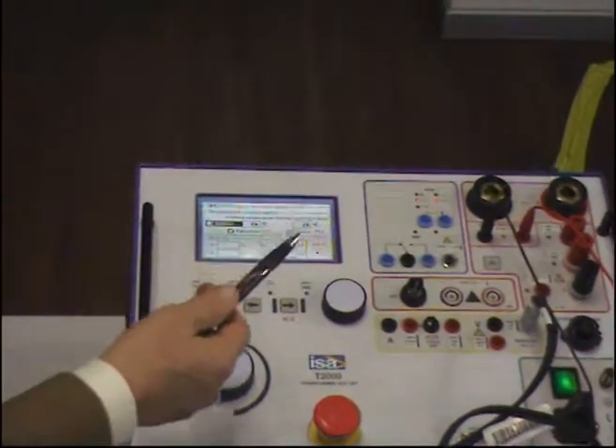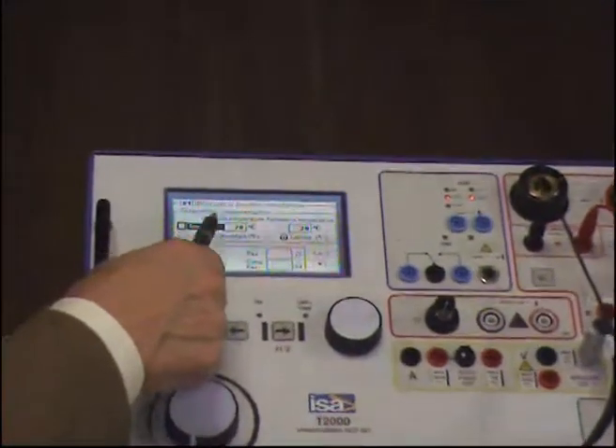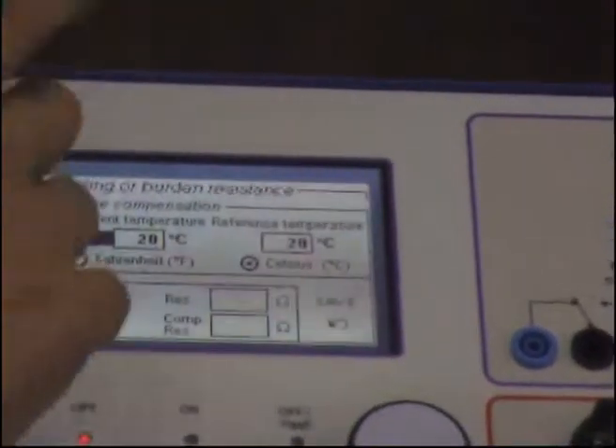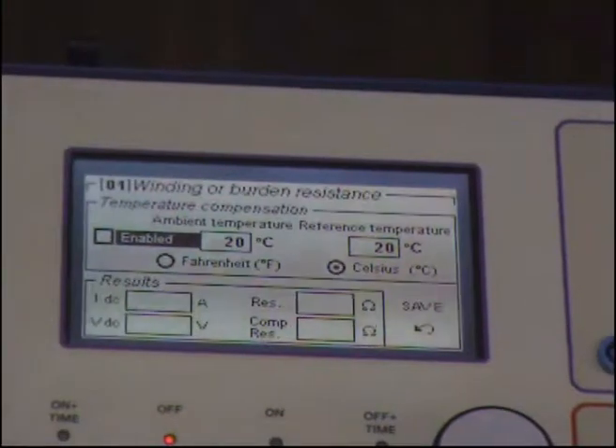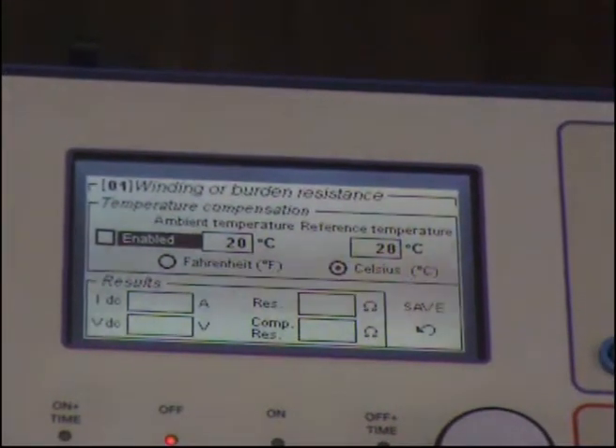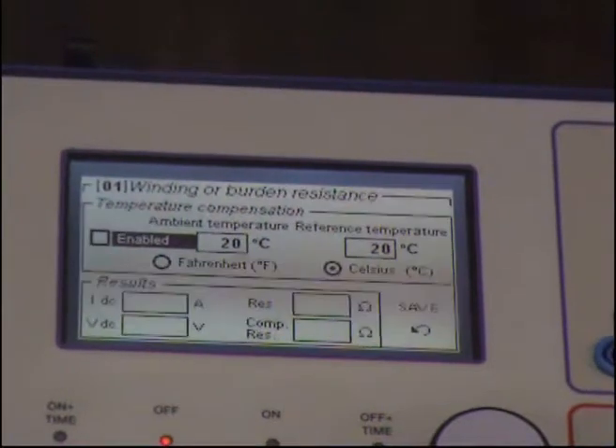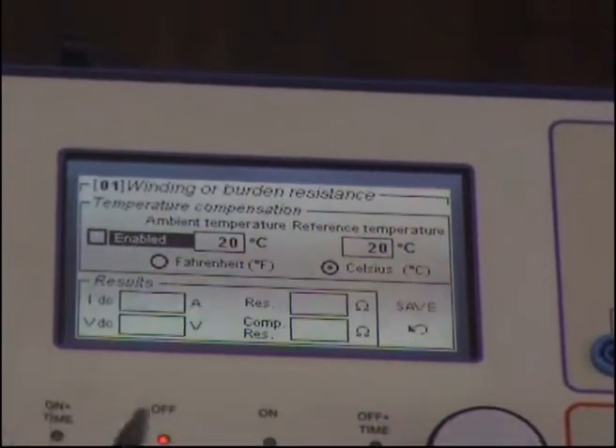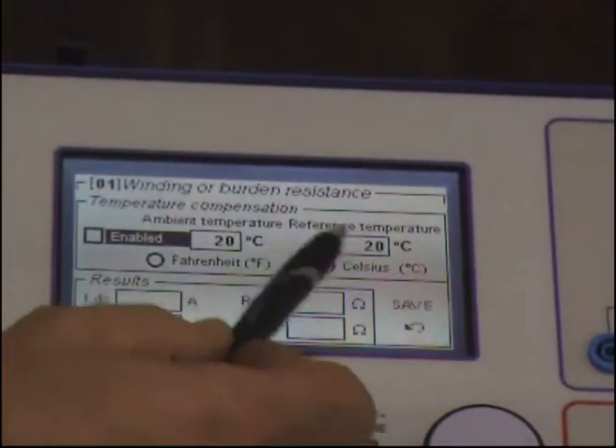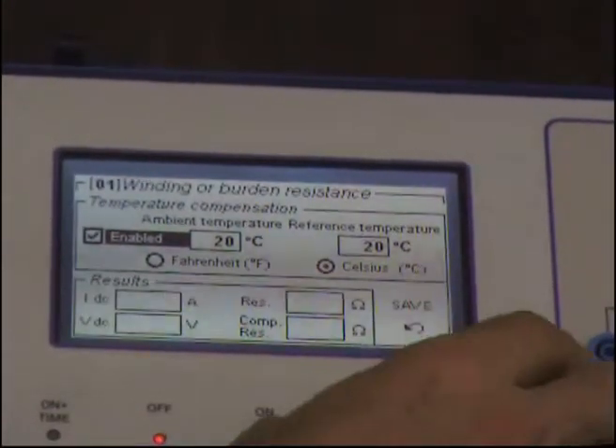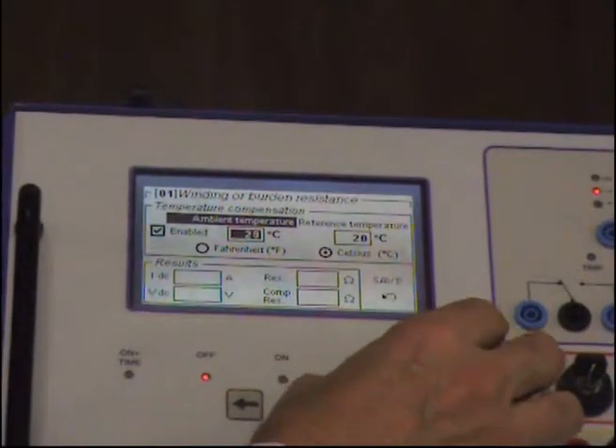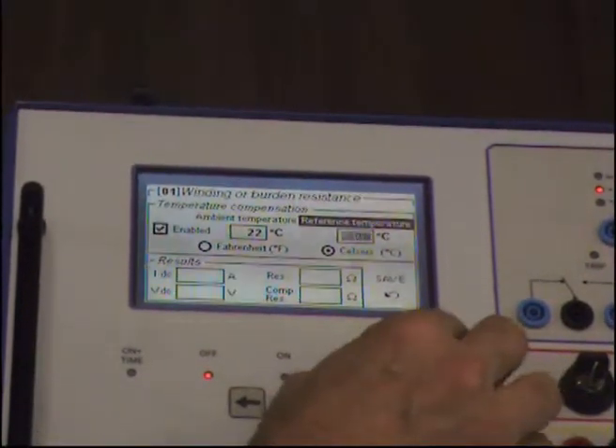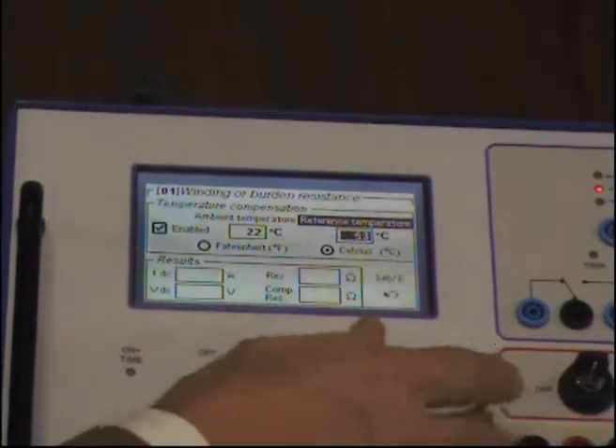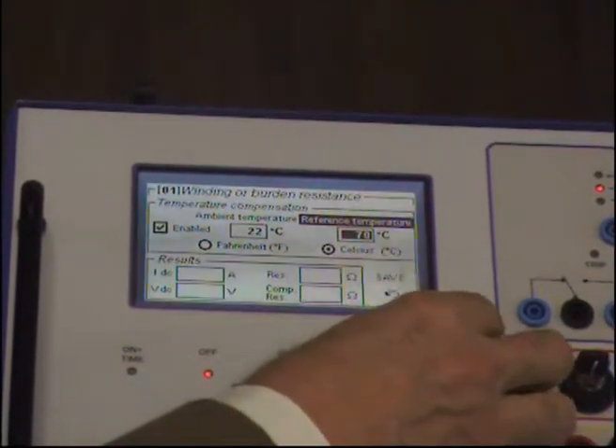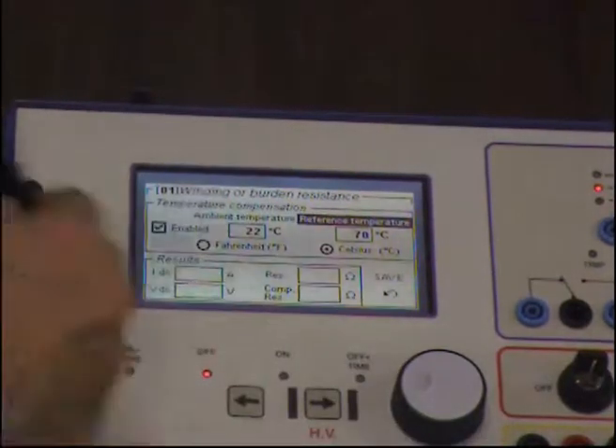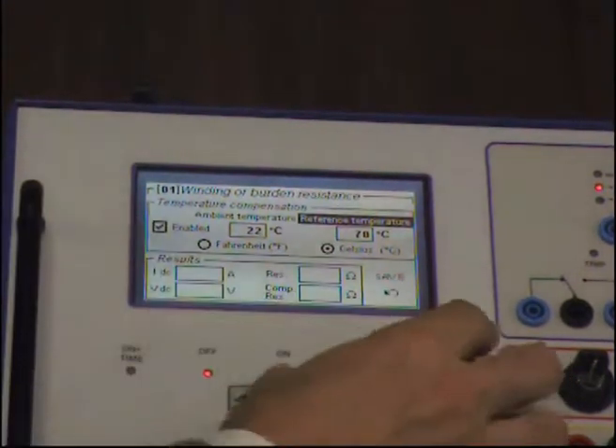So what can we do? First of all, the purpose is to compensate for this change. We know the temperature coefficient of the copper, and we can know what the resistance would be at the reference temperature. So I can enable this. I can say here that the ambient temperature is 22 degrees C, and I want the reference temperature, for instance, at 70 degrees C. And you can have the choice between Celsius or Fahrenheit.